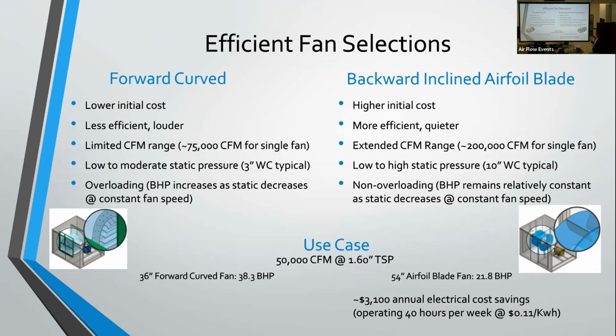Backward inclined airfoil blade fans, although they do have a higher initial cost due to their design and construction, are more efficient and quieter. You have a much larger CFM range with them, up to 200,000 CFM with a single fan. That's for a single inlet plenum fan, but way higher CFM ranges. But more importantly, static pressures. You can run these fans at a way higher static pressure than your forward curve fans. Think of them like a bulldozer. They push that air, versus your forward curve fan, which is just trying to kind of throw that air, almost like a baseball. And these fans are non-overloading, so with that same comparison to your CFM, as total static pressure decreases, your brake horsepower stays relatively the same, so you don't have to worry about overamping those motors in those situations.